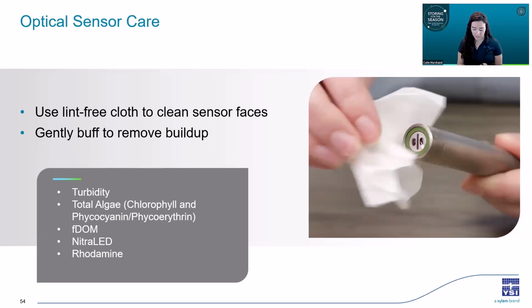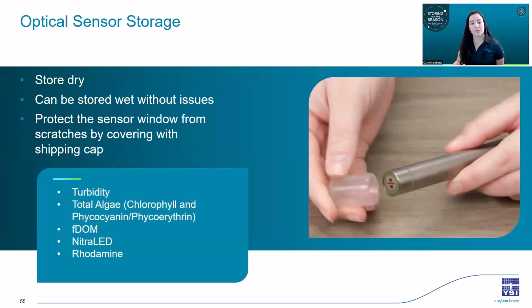But some sensors like the EXO and ProDSS optical sensors are made with sapphire windows, which are harder than glass, and they can be gently buffed to remove buildup and won't scratch easily. And then optical sensors can be stored dry, like the CT, though they can also be stored wet with no issues. To prevent scratches, you'll just want to cover the sensor tip with a shipping cap like this one here, and also cover the connector end if you removed it from the instrument.